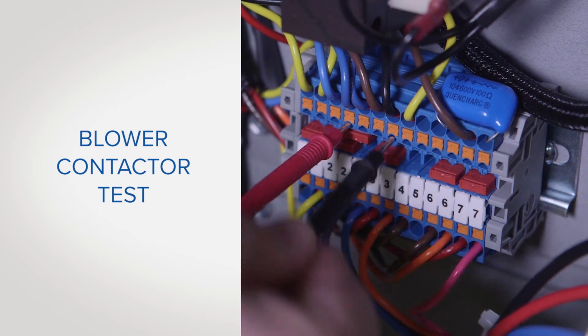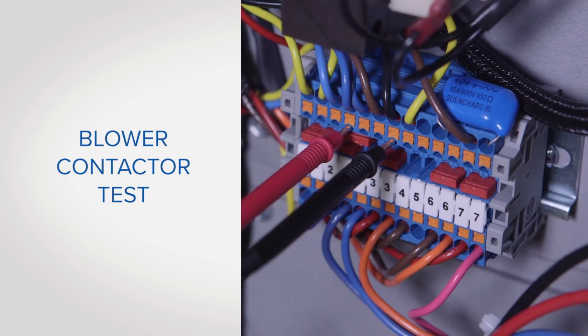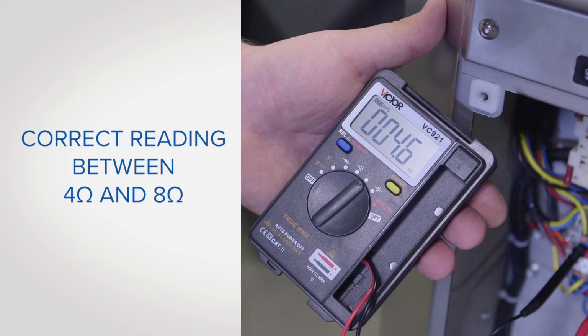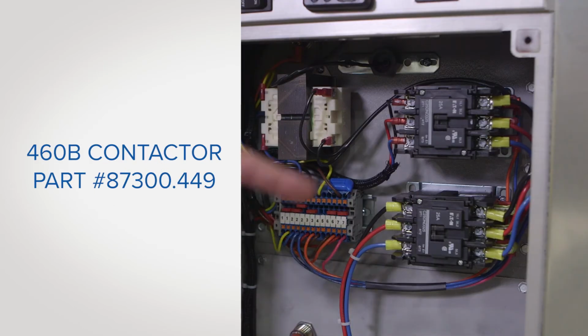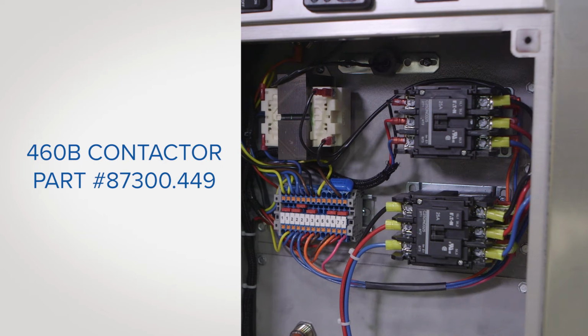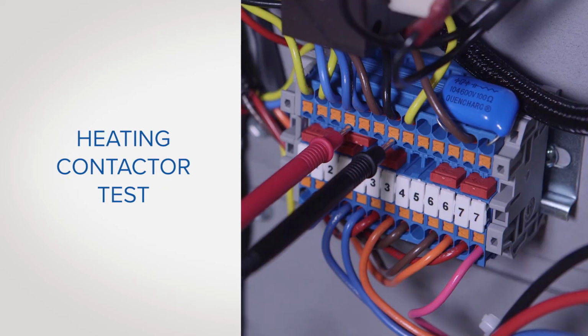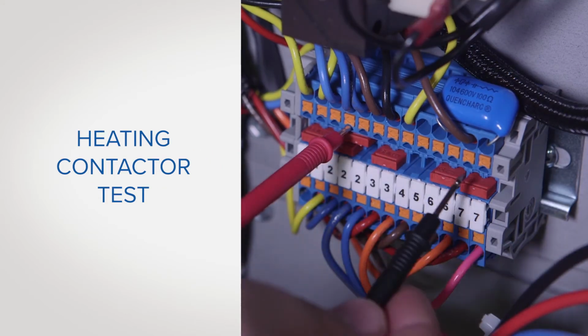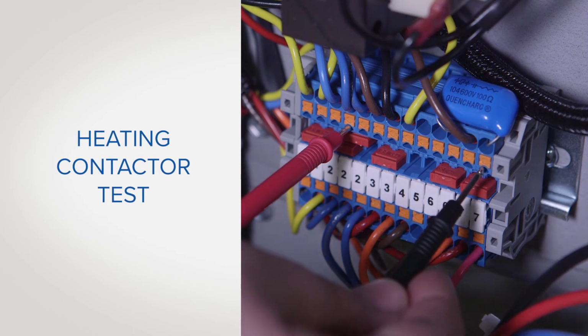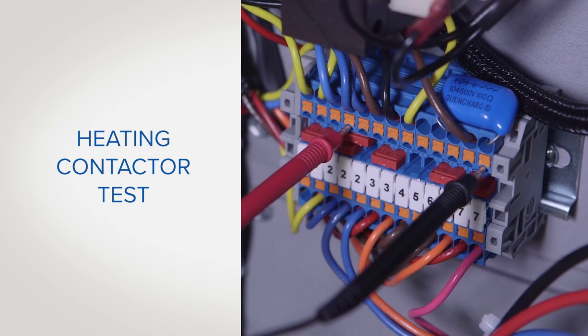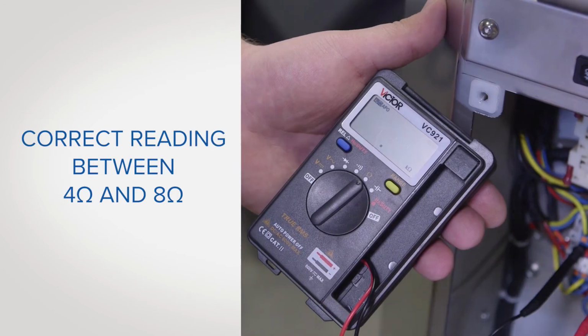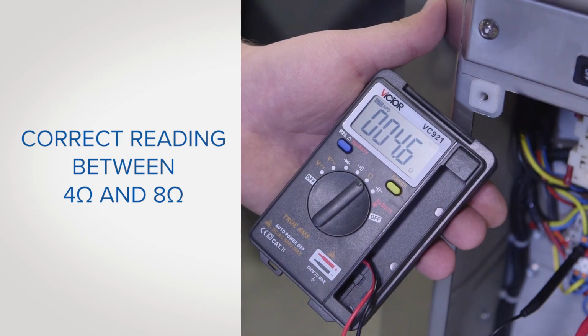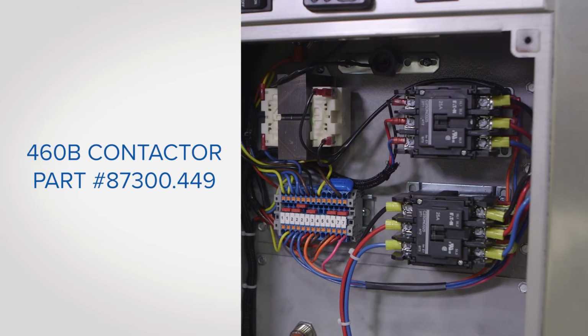Next, test the blower contactor. Place the ohm meter on the lowest scale and read between the first terminal 2 and 3. The reading should be between 4 and 8 ohms of resistance. If your reading is not within that range, you will need to replace the 460B contactor. Next, test the heat contactor. Place the ohm meter on the lowest scale and read between the first terminal 2 and 7. The reading should be between 4 and 8 ohms of resistance. If your reading is not within that range, you will need to replace the 460B contactor.